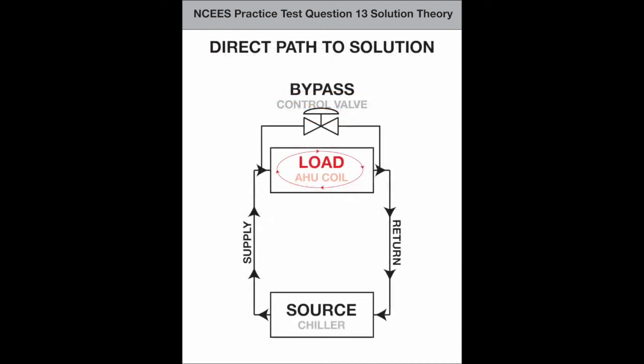The coil load is the thing the AHU is demanding to cool the air it is handling. And it is the thing the chiller is sending the chilled water to. So, you have one valve on the bypass leg, which must, at a minimum, accommodate the pressure loss of the coil in the AHU which it bypasses. That is, it must have design flow capacity to take on the pressure drop of the load, plus the pressure drop of the valve itself.